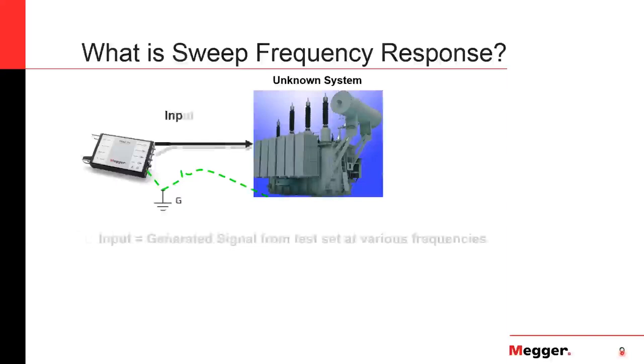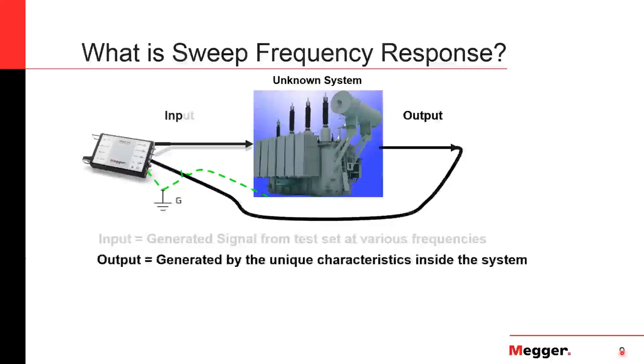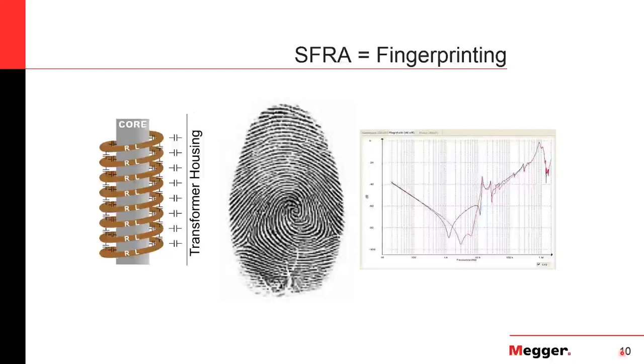With frequency response analysis, we have an unknown system — your transformer. All we're doing is putting a signal through various parts of the windings and measuring the output on a corresponding secondary. Looking at output over input, we get a response for that transformer. The transformer, viewed as an RLC circuit, is unique in its design — basically every large power transformer is a custom design and will come out with its own unique fingerprint.